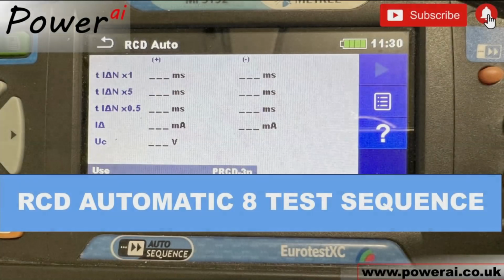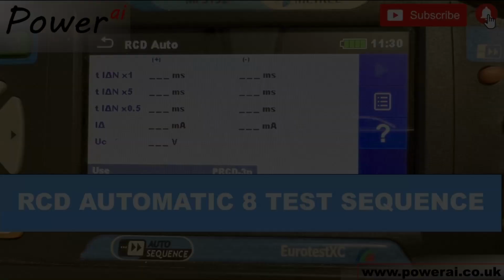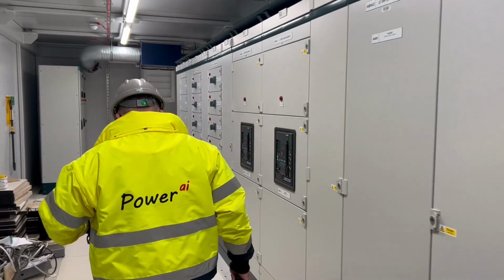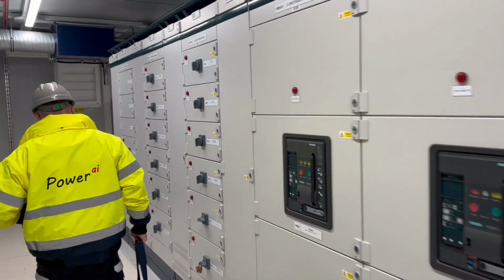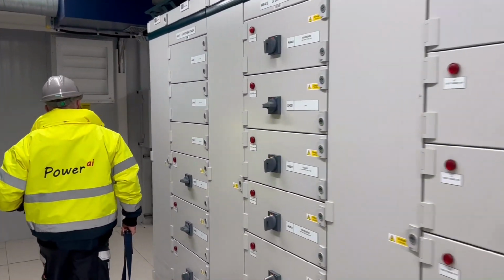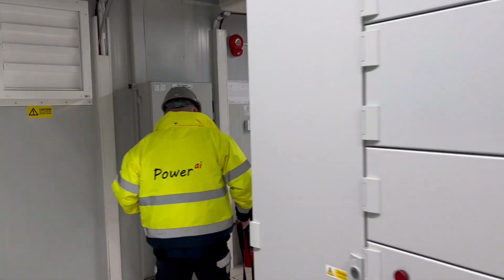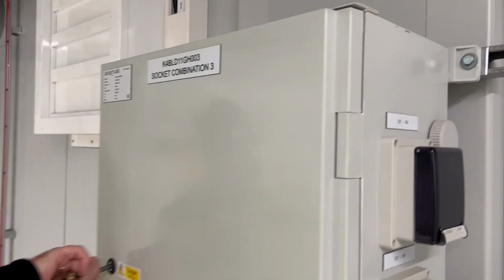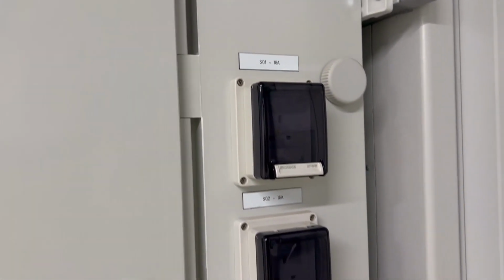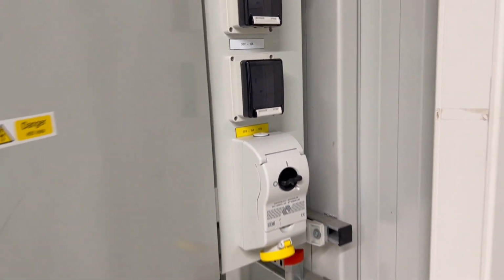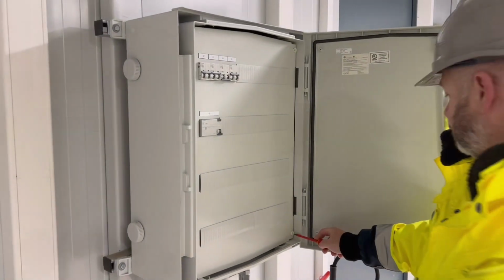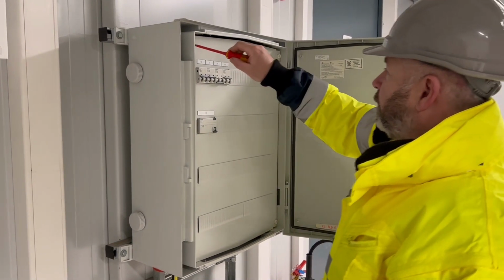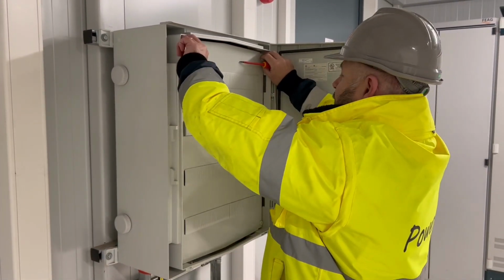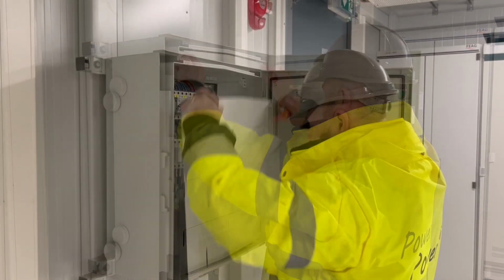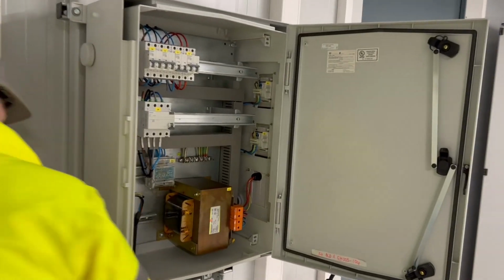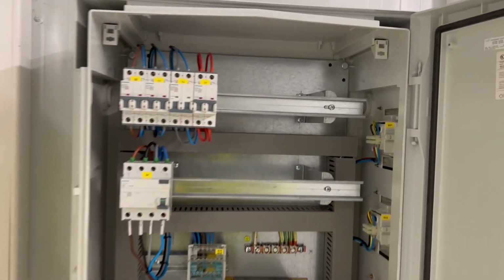In this video we'll be testing an RCD on a socket box which is used for connecting portable tools and equipment via a centre tap earth transformer which is internally fitted. We've been requested by Siemens to check this unit and to make sure that it complies with BS 7671 18th edition wiring regulations, as this part of the entire installation was designed under 7671.